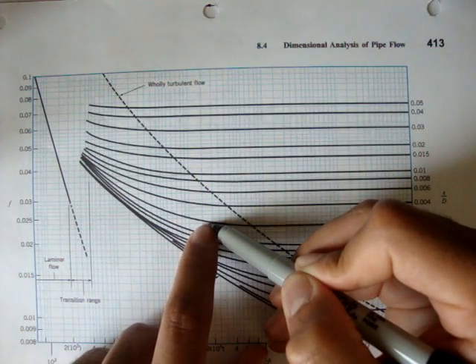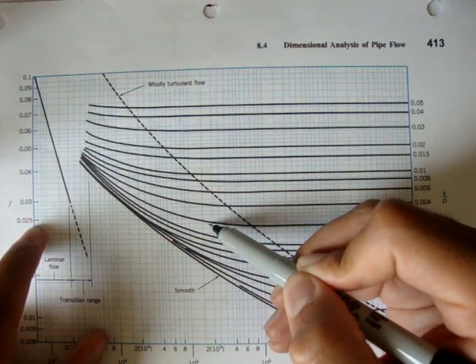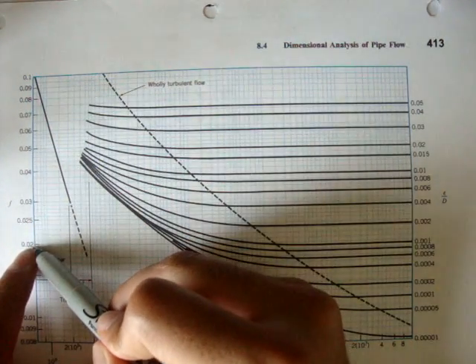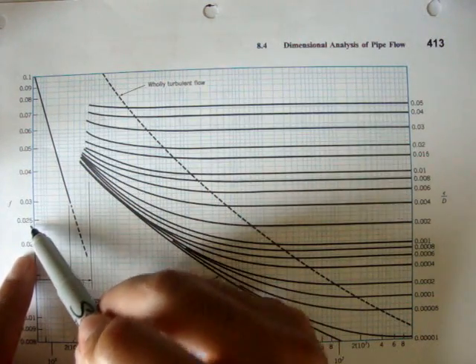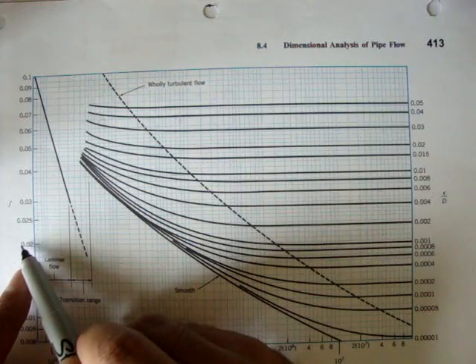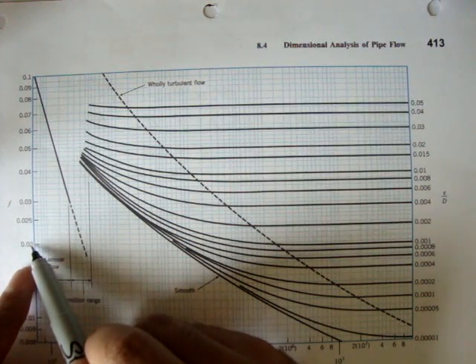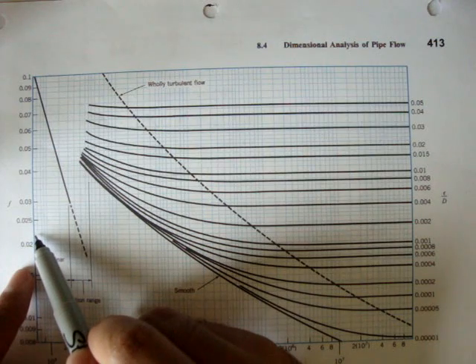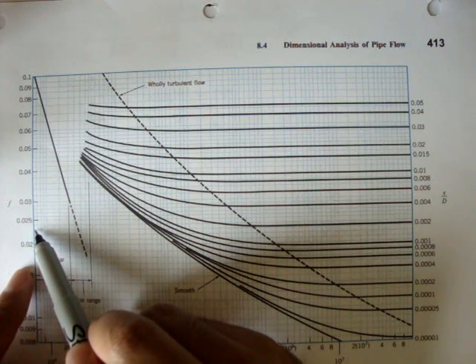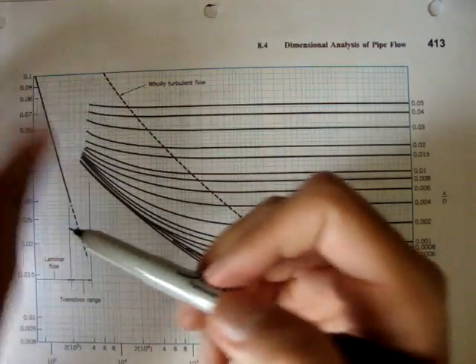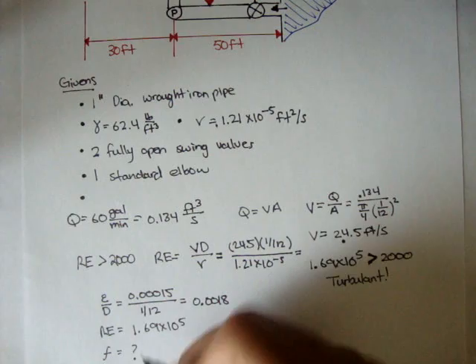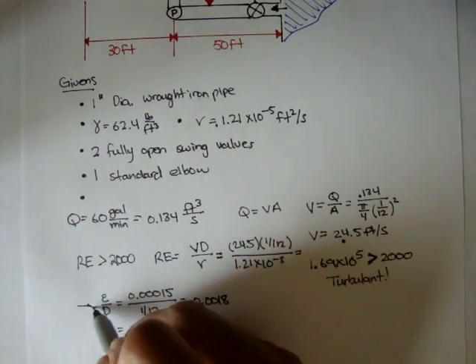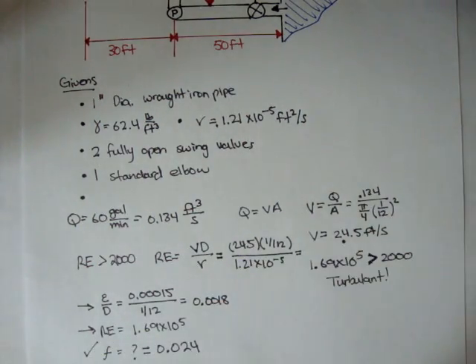And if we use that intersection to find our frictional factor, we see it's 0.024, right? Because this is 0.02, and this is 0.025, and there's 5 blue lines in between. So it increases by 0.001. So this would be 0.02, 0.021, 0.022, 0.023, 0.024. So our frictional factor would be 0.024. Using the relative roughness and the Reynolds number, we found the frictional factor.